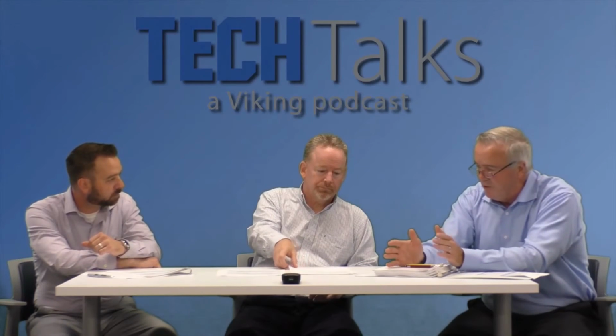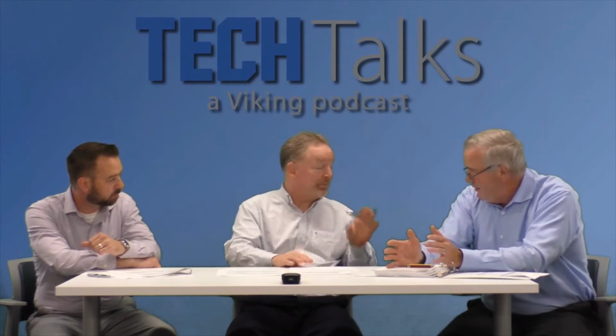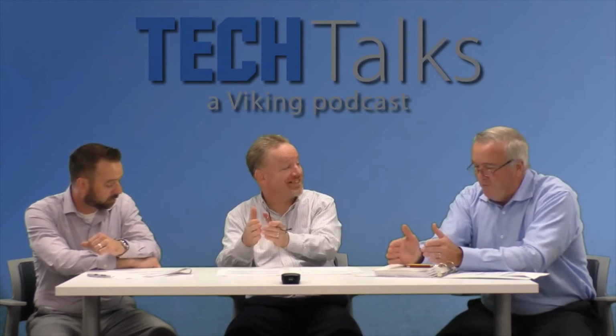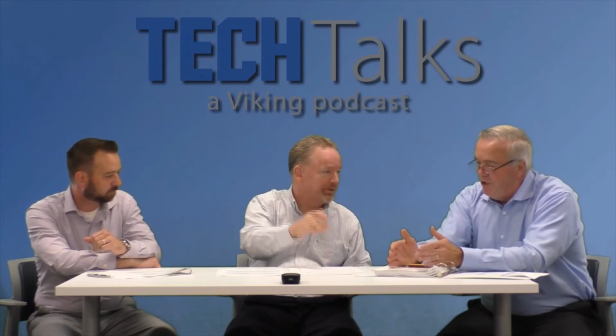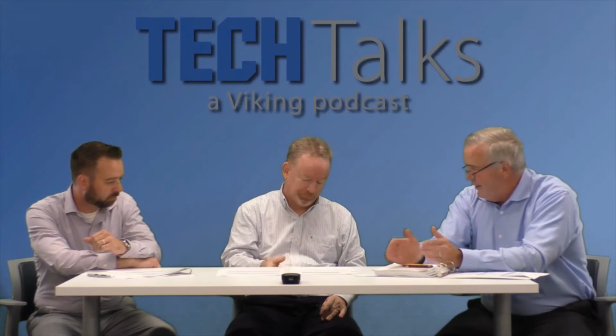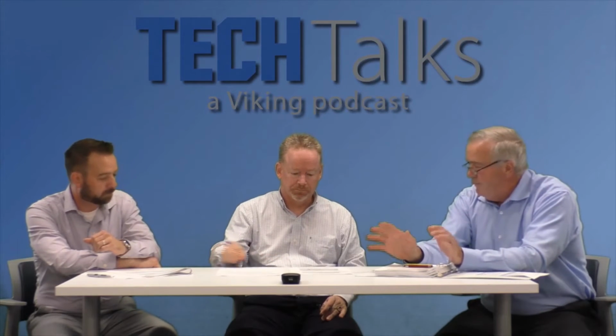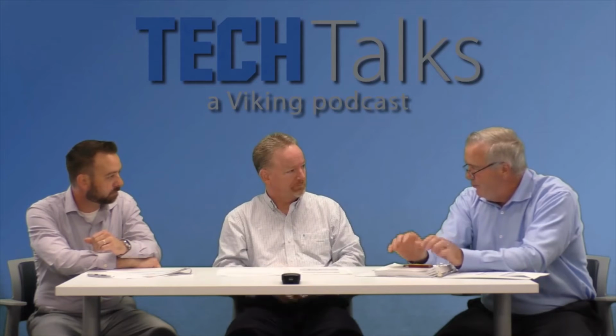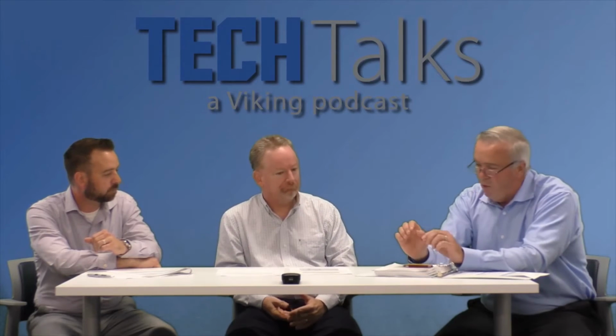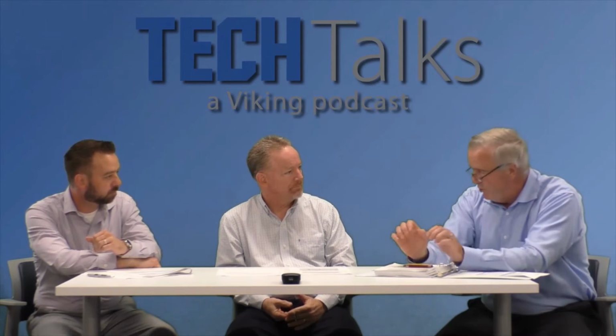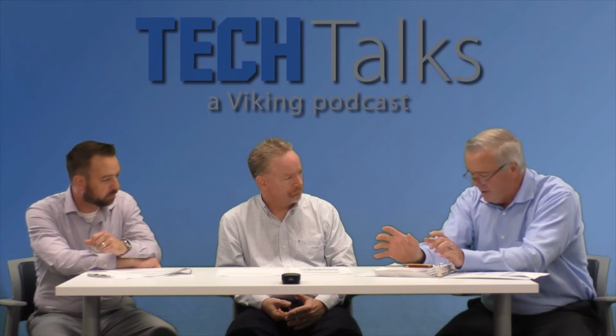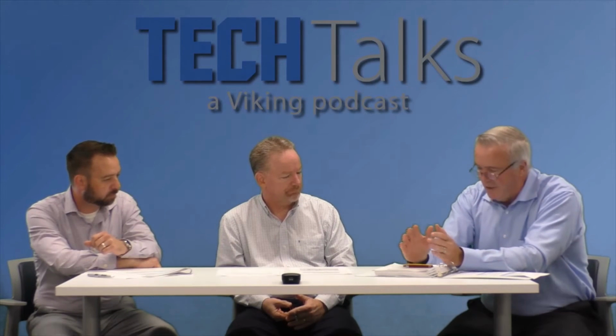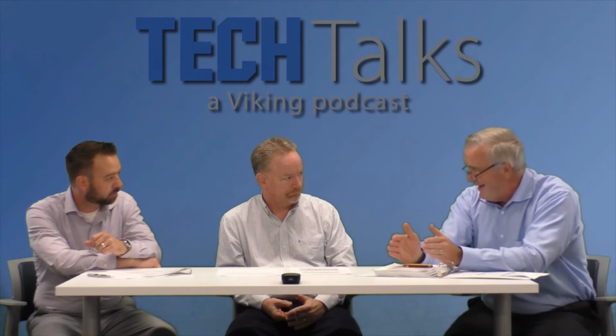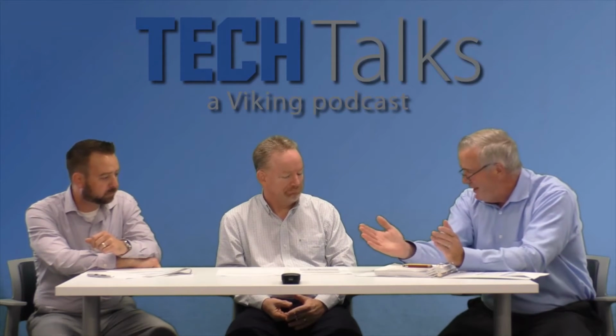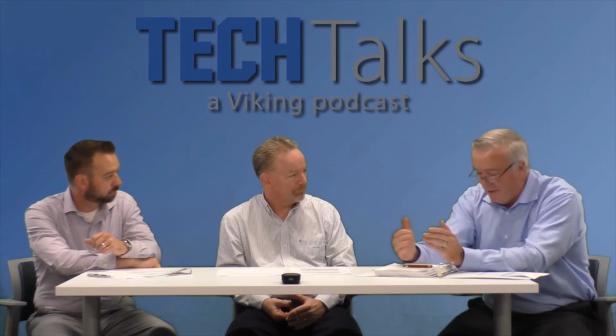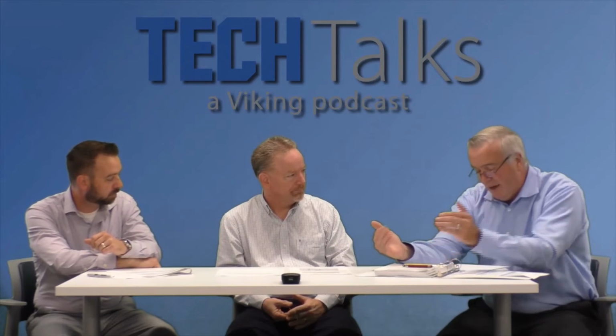So for 9 sprinklers in Table 17B, that's the key. If you go to 17B, it's a 9 sprinkler design, you can use the main 3, 3, 3 paragraph, and that's for both ceiling slopes. For 10 sprinklers, it's either going to be 3, 3, 3, 1, or 4, 4, 2, depending on the ceiling slope. And that's another one where you just really want to make sure you're getting that right, because that could pick up another sprinkler on a branch line.